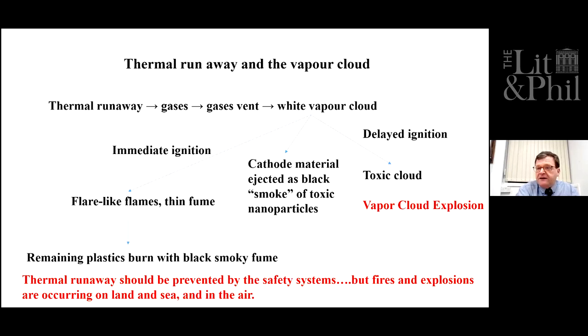If, however, it doesn't ignite immediately and you get delayed ignition, which has happened, then you can get a vapor cloud explosion. A vapor cloud explosion can give rise to overpressures on the order of 6, 7, or 8 atmospheres, and a tenth of an atmosphere is sufficient to kill you.